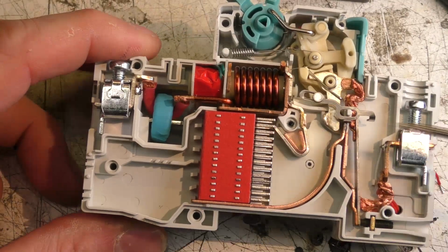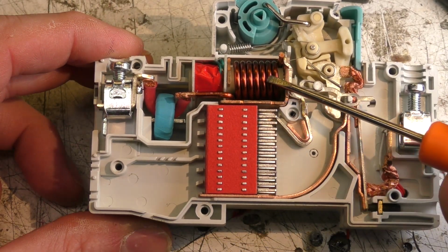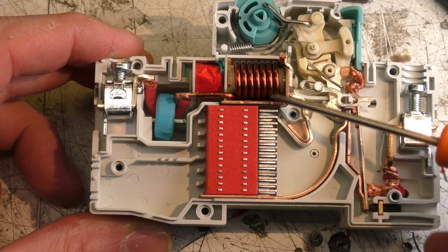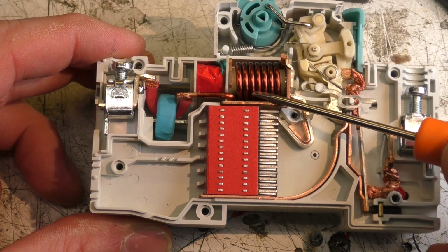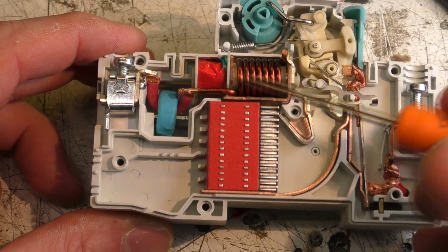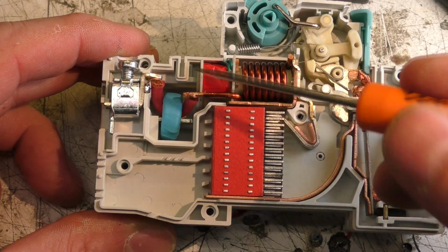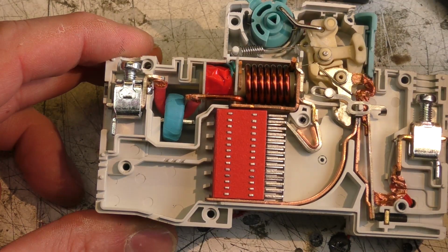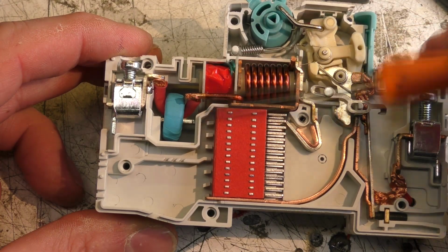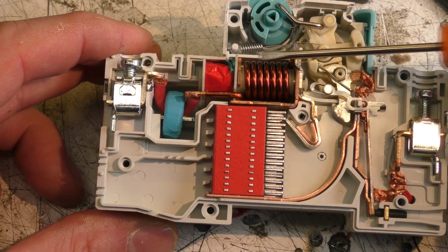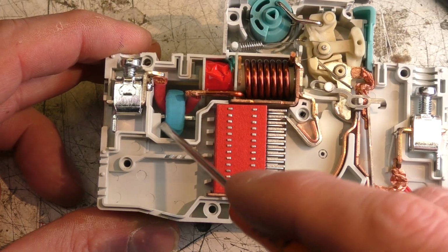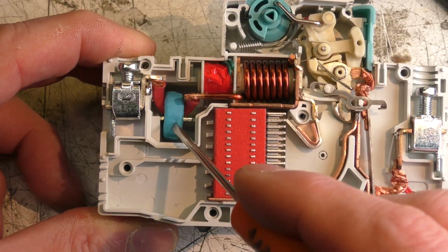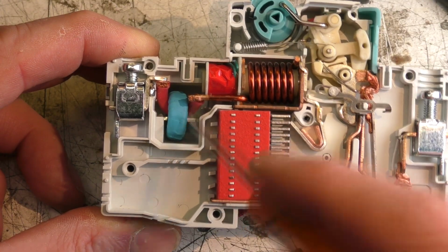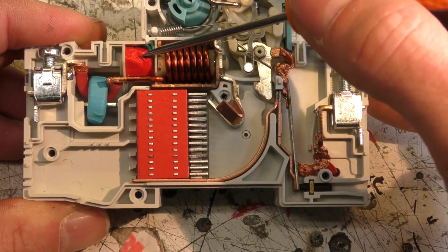Okay, on this side we've got a conventional circuit breaker. We've got this coil around the trip mechanism, so that's going to provide the fast tripping on very high overload currents. There's a coil around here which passes through to the other side, so that's how the controller can trip it in the case of an RCD fault, maybe also lower overcurrent faults. There's a current transformer here which goes across both live and neutral, so that's going to be the sensing coil for the RCD functionality. That's what these two pink wires are. Two green wires will go into this trip coil.